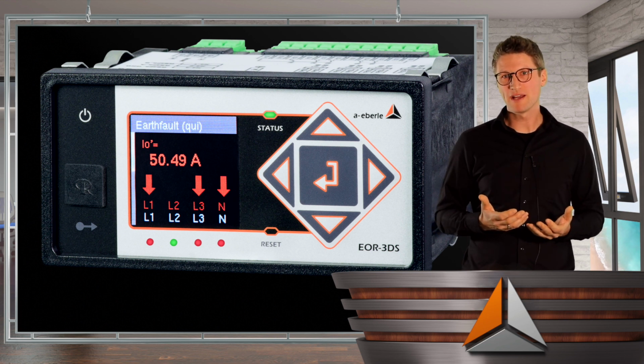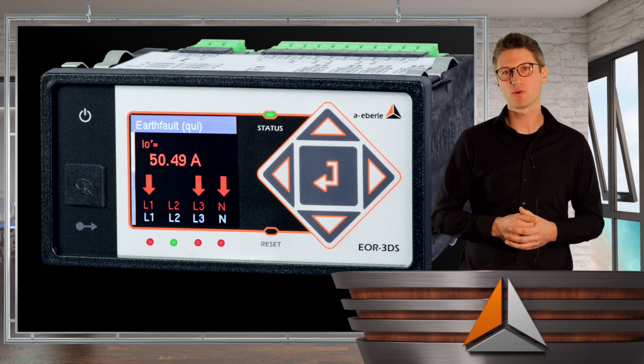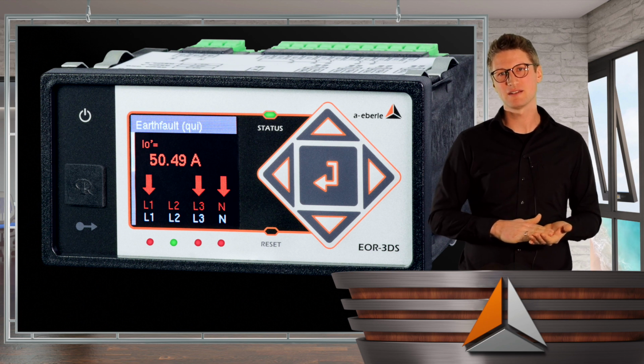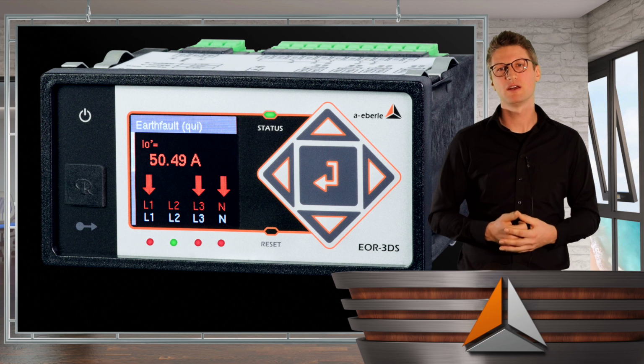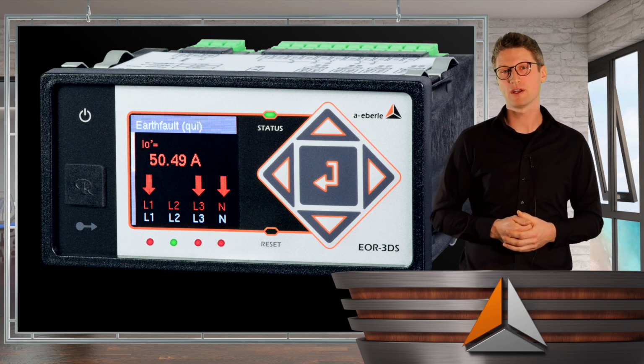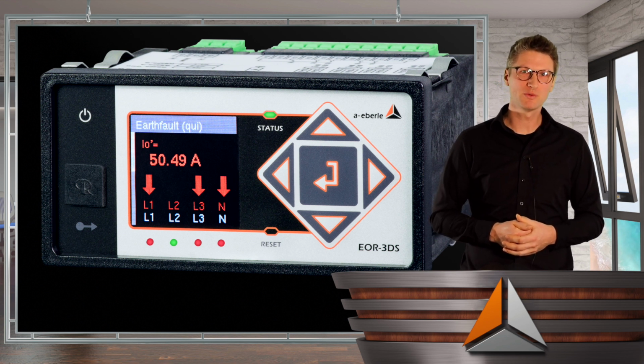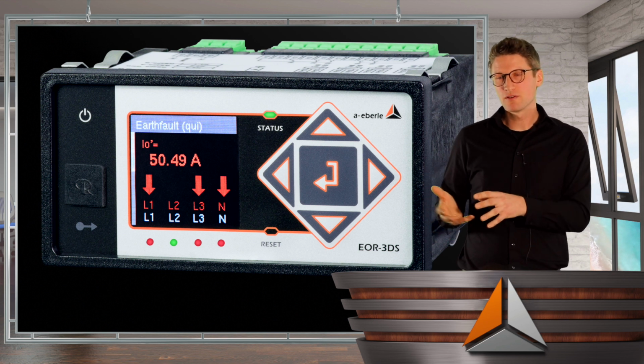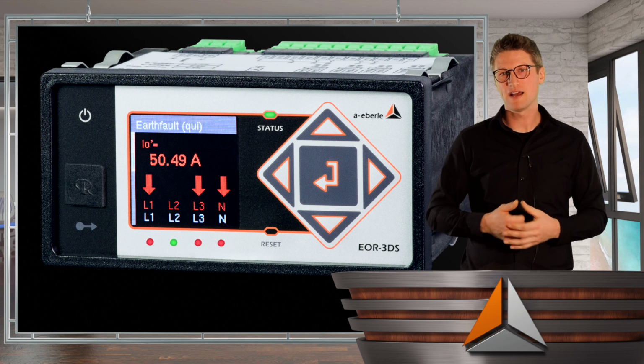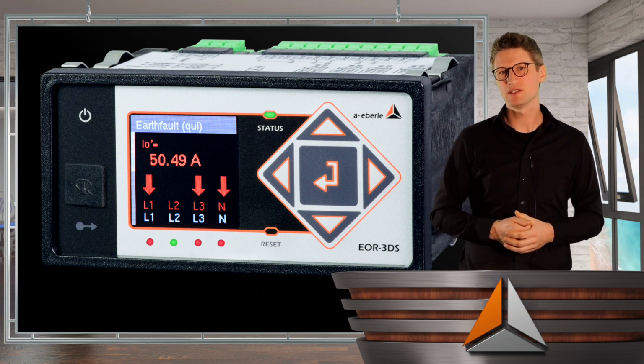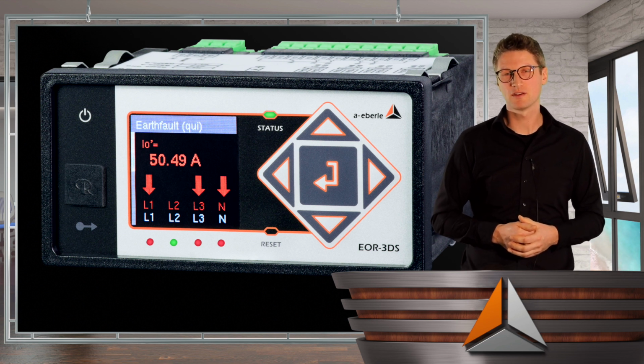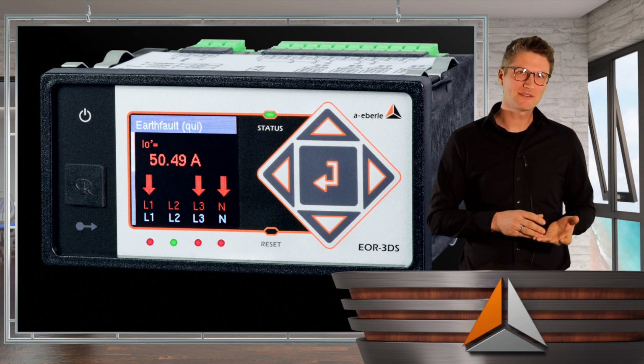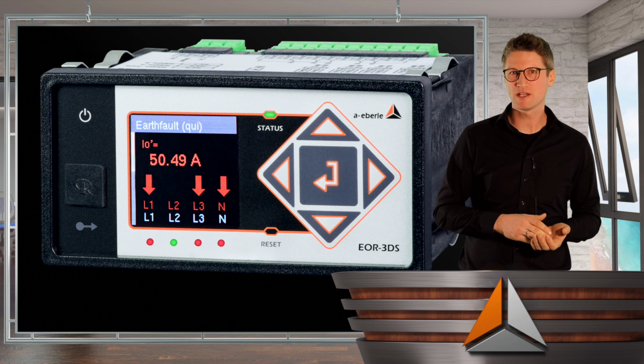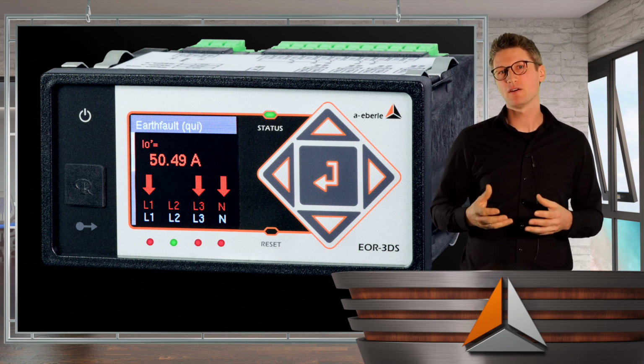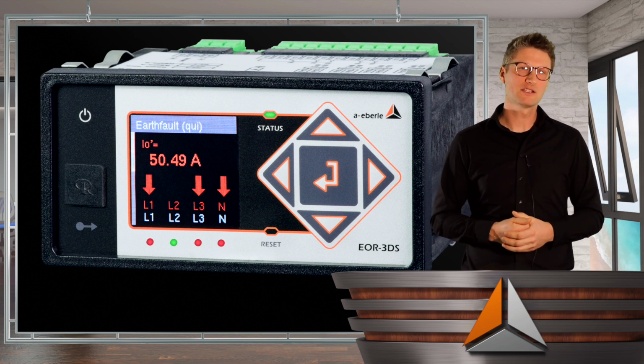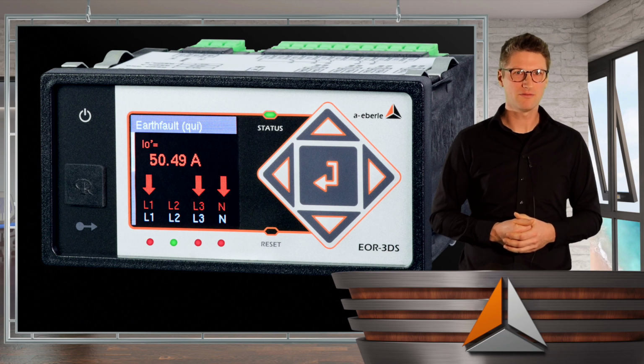We are compatible with a very wide range of low power sensors, have free programmability, so a PLC functionality in the device, and the device is capable of a lot of standardized SCADA protocols like 104, 101, 103 protocol, 61850 GOOSE, DNP and Modbus. In addition to these traditional SCADA protocols, the device also supports MQTT IoT and MQTT management and operations, including a sophisticated certificate handling. The device EOR-3DS has a DC wide range power supply from 20 volts to 148 volts, because AC power supply is not so common in digital secondary substations, because they are often power supplied by a battery.